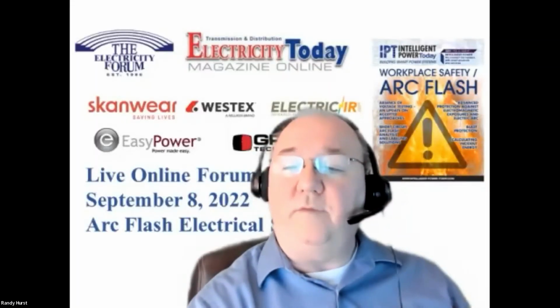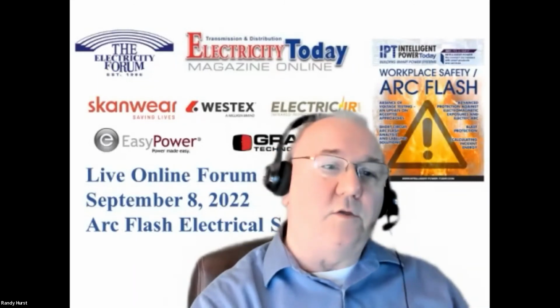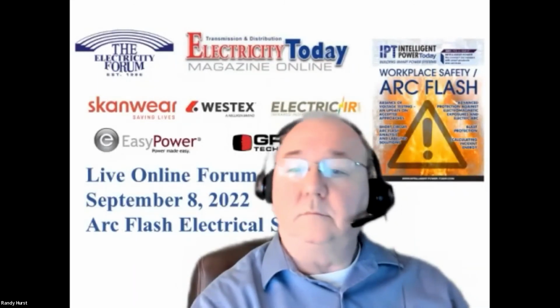What type of head and face protection and ratings do you have? As a business, we have hoods up to 65 cal and 40 cal, plus various helmet and visor combinations with balaclavas ranging from 12 cal through to 28 cal. We always recommend that above 12 cal you wear a hood as per NFPA 70E, rather than just a helmet, visor, and balaclava combination.